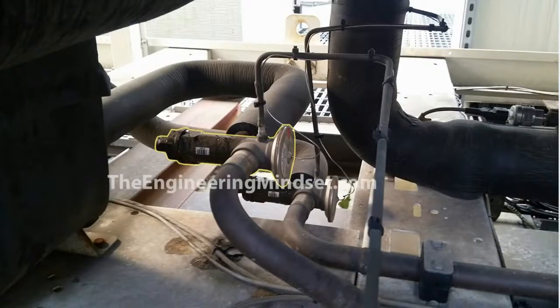Now these types of valves are usually found on smaller chillers. As they start to get larger, that's when they move over to the pilot operated valve to give much better control.